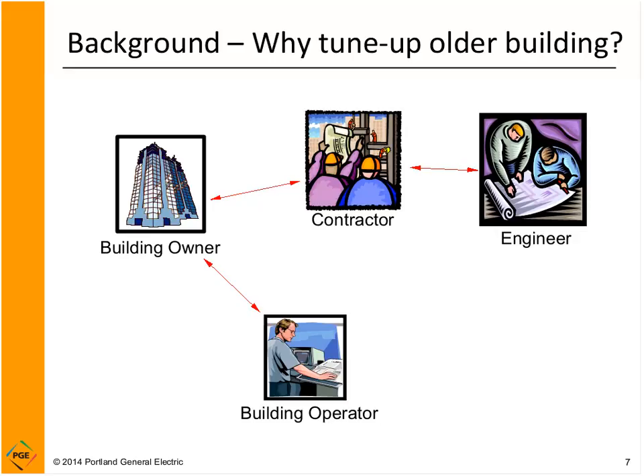The building operator has to respond to the building owner's requests and ultimately respond to tenant needs. So if the operator is working on complaints from tenants about temperature, they have to figure out a way to satisfy the occupants. One way to satisfy temperature complaints is to, for example, lower your chilled water temperature, and that may solve the problem if tenants are too cold or too warm.